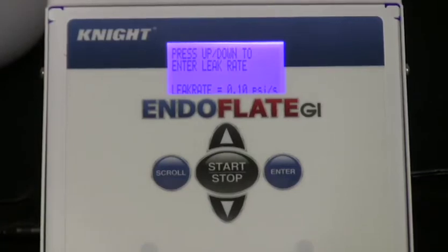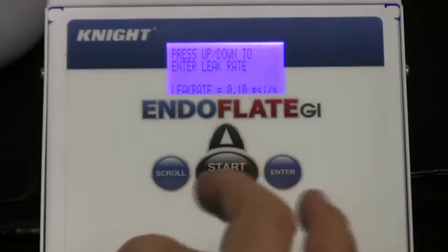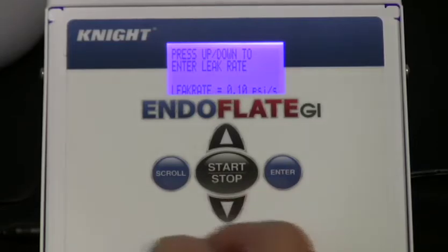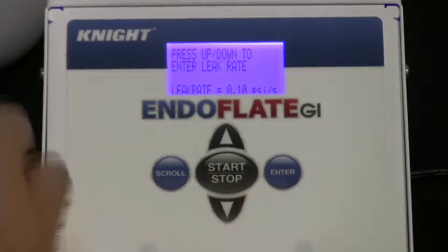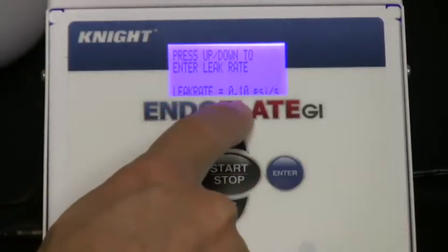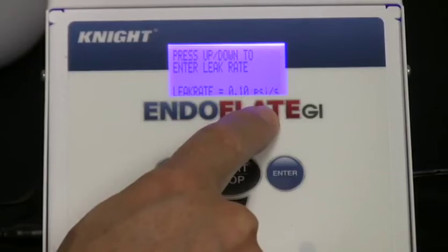You know, an air leak in an endoscope or in any inflated diameter can be very, very small. Granted, I'm learning about this myself, but you would be surprised how much a single bubble, how large a space that single bubble of air can fill. From the factory, the way we're going to calibrate these initially is going to be at a leak rate of 0.10 psi per second. Okay, now that's a very small leak, but a leak nonetheless.